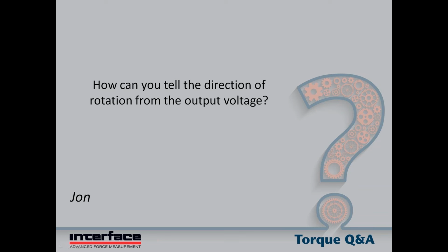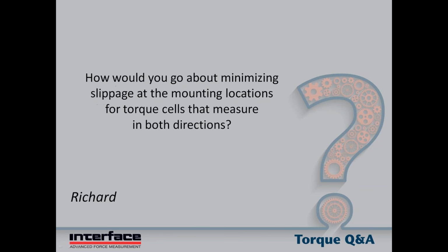So you really can't tell the direction using the voltage, but in many cases these torque sensors can have an encoder installed in them, and that encoder can be used to tell the direction of rotation. A single track encoder just pulses with rotation and gives you RPM, but a 2-track encoder, which most of our sensors are available with, can actually look at the 2 tracks' relation to each other, and that can be used to determine the direction of rotation. So, good question. Hey, Keith.